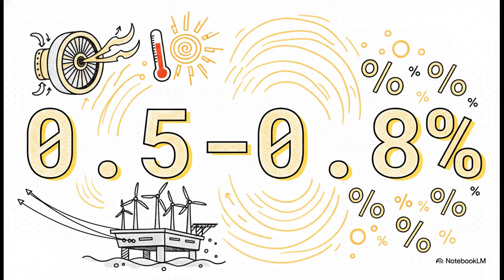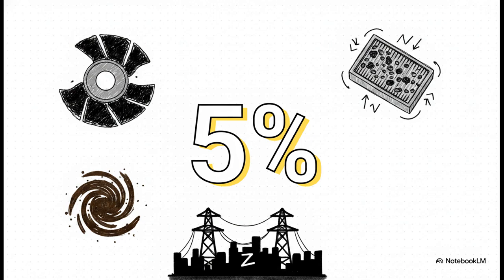Just think about our offshore platform operating in 40-degree heat. You're 25 degrees above the baseline. Multiply that by an average 0.65% derating, and wow, you've suddenly lost over 16% of your total power generating capacity before you've even flipped a switch. But wait, it gets worse.